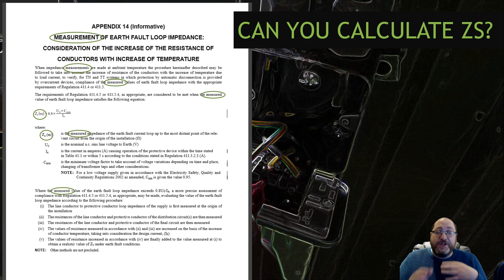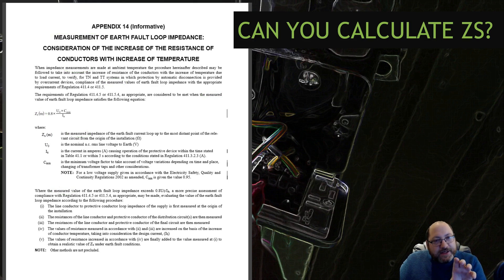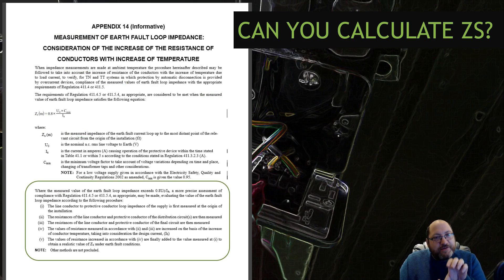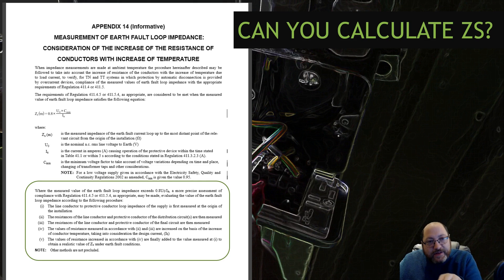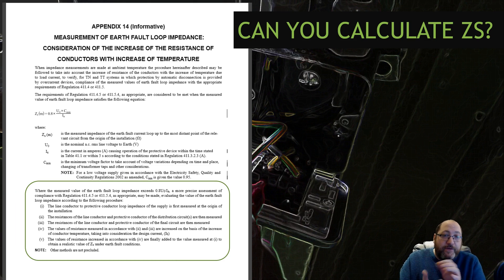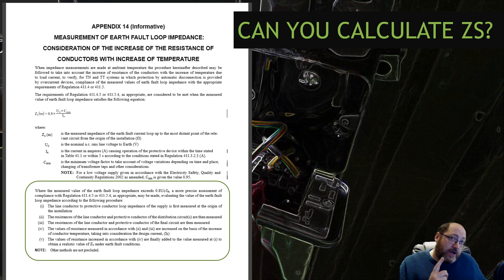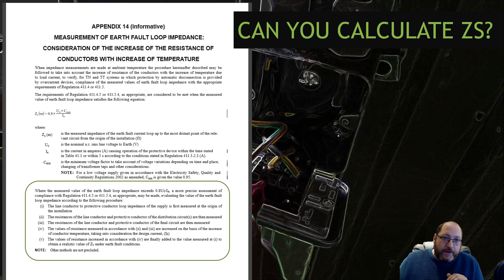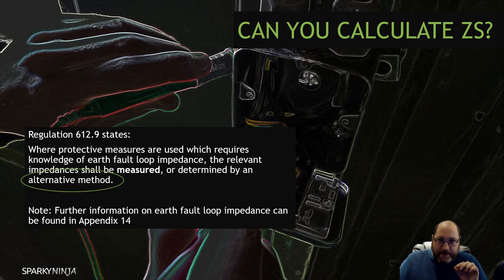That is the standard route — the standard route is to measure. There's no question of calculation as the first approach here. However, further down it does say: if your measured value of the loop impedance doesn't exceed the 0.8 × U/IA calculated value, you can then assess the line conductor and protective conductor loop impedance. So it says you can calculate, but that's calculating to verify a measurement you are not satisfied with.